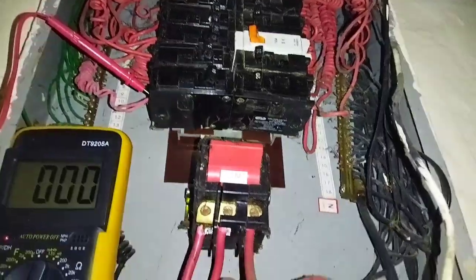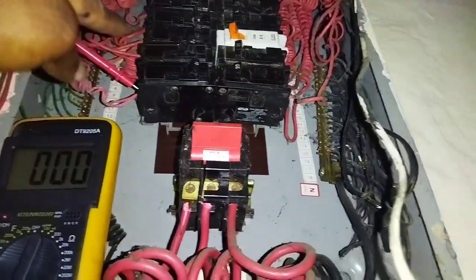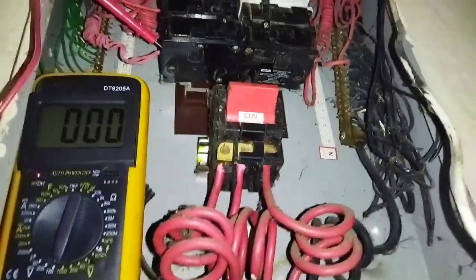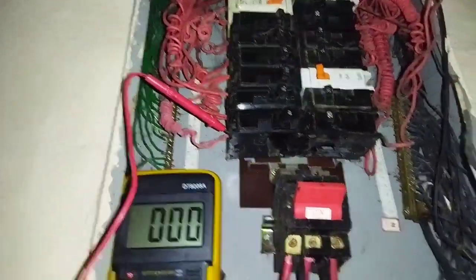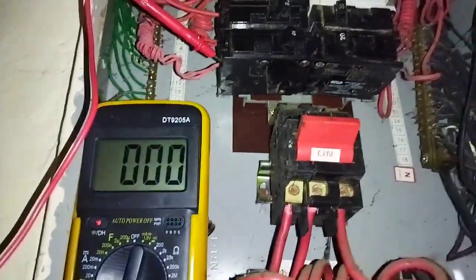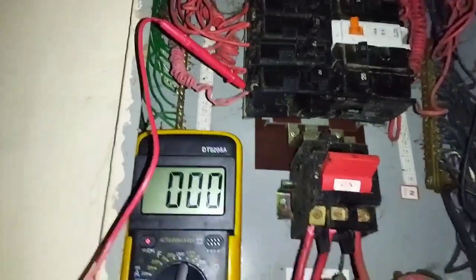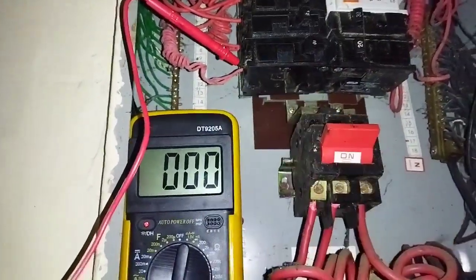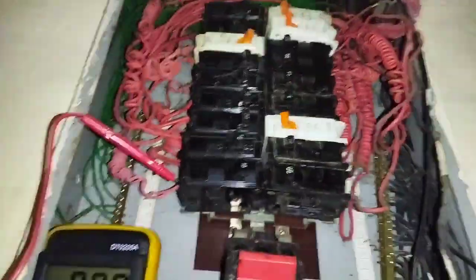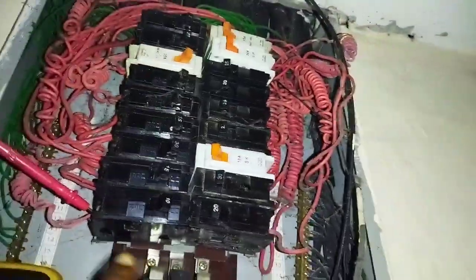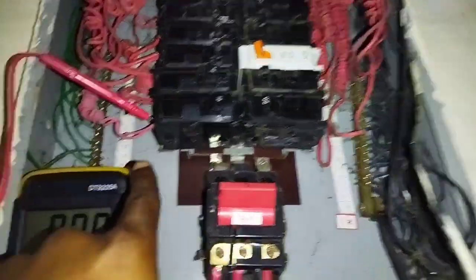But bear in mind, if there is a fault, a short circuit, or a breach at the load point, you have to verify very well before you replace the breaker or put it back on. As I said before, some breakers can be faulty and remain in the on state, but the output is not functional. The only way you can test for this is to either pull out the breaker and test for continuity between the two terminals, or, when it is connected and there is a load, test for voltage between the output terminal and the neutral link. So that is it for circuit breakers, guys.